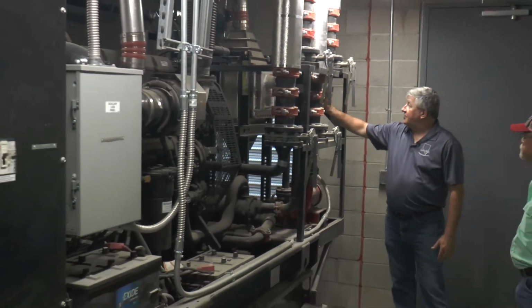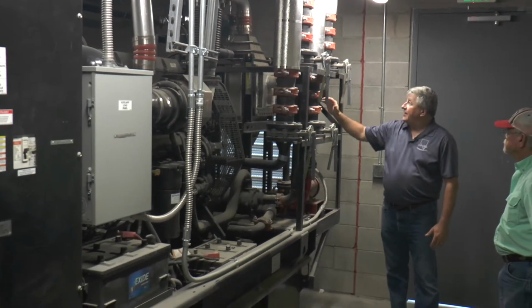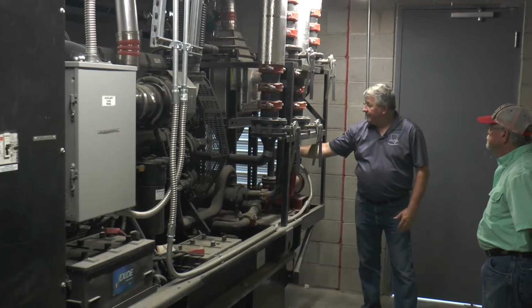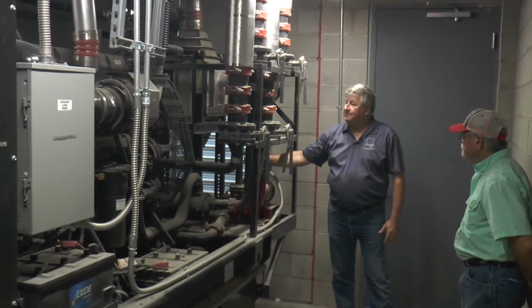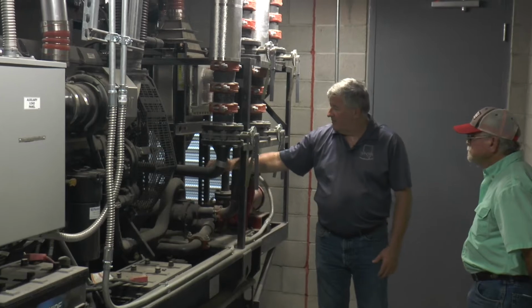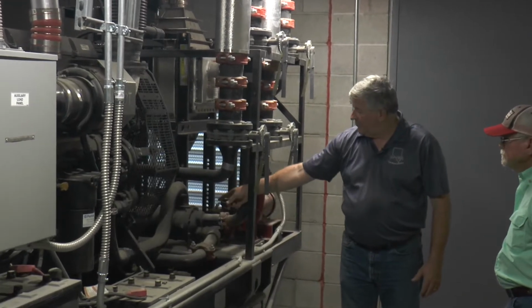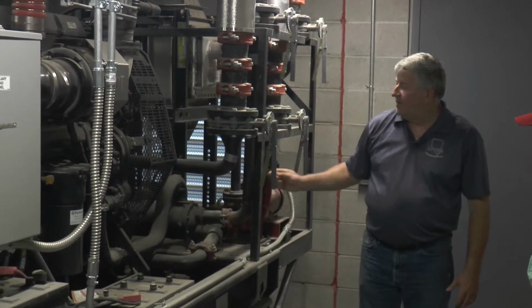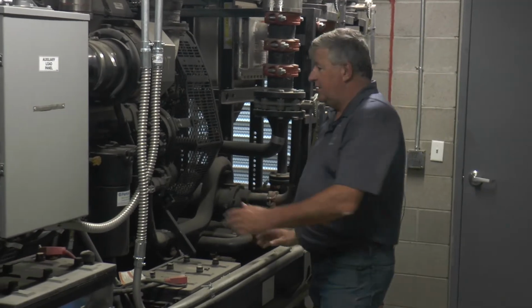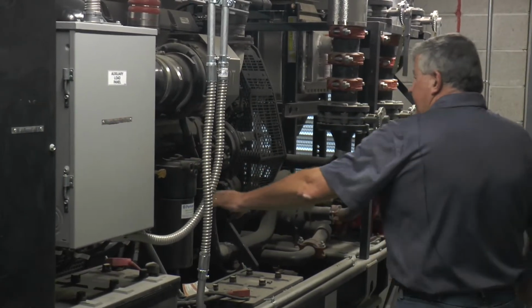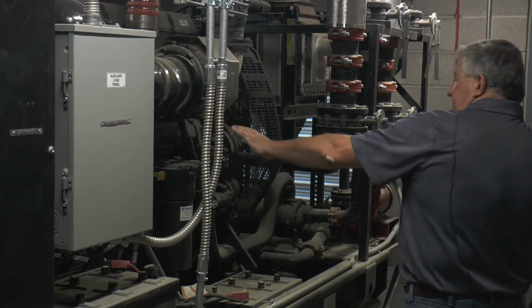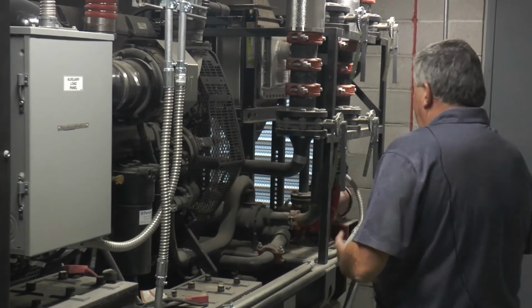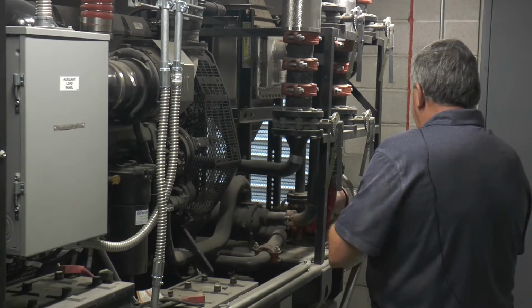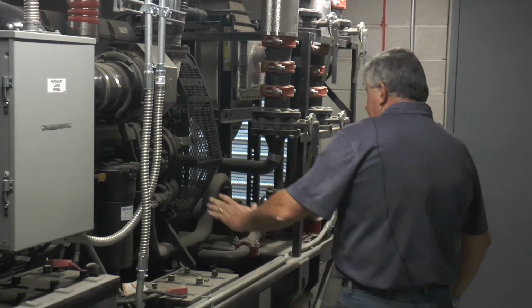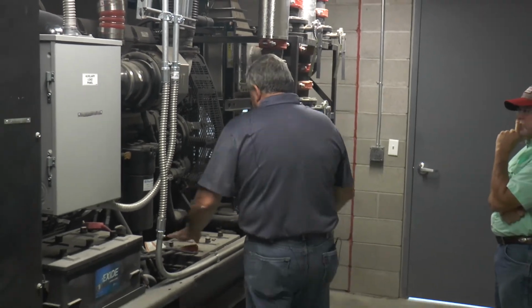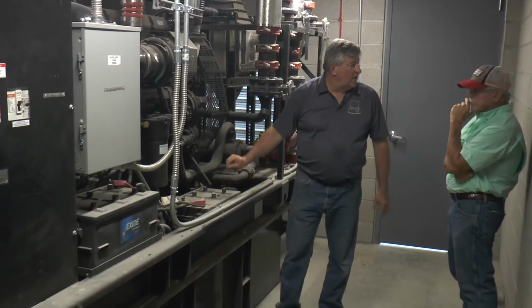So there's isolation valves going through. Like I said, this is the charge air cooler. This is the water lines going in. Top and bottom are the air lines going in from the engine. Jacket water, supply and return coming in, going through a shell and tube heat exchanger. This side of the engine, you're going to have your oil filter. As I said before, just look around the engine, look for water leaks, any type of coolant leaks or anything like that. Engine batteries are lead acid.